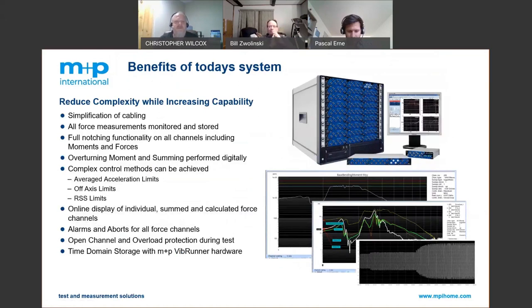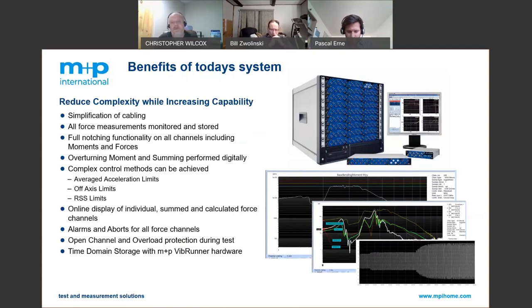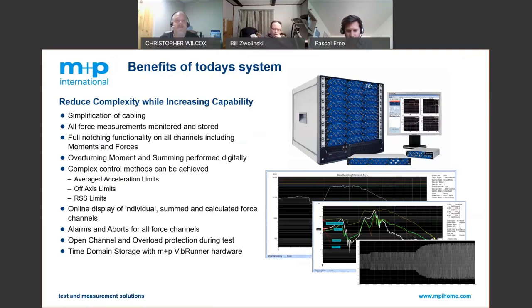The benefits of today's high-technology systems: number one is simplification of cabling, which is very critical in the real test world as cabling is one of the biggest problems encountered. All force measurements are monitored and stored; they can be used for center-of-gravity calculations and individual sensor anomaly detection. Other benefits include average acceleration limits, off-axis limits, and off-axis monitoring — if a force sensor cannot be mounted in the exact X-Y orientation, you can adjust for the angular offset in software. Everything is available online, and standard alarm boards used for 30 years are still available.